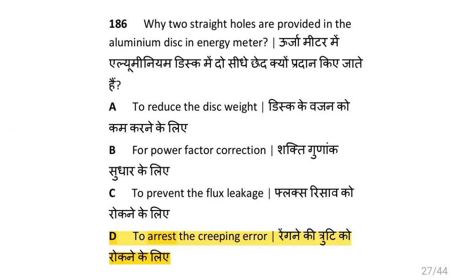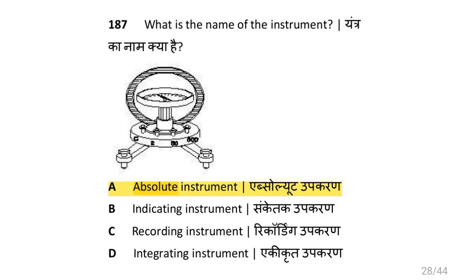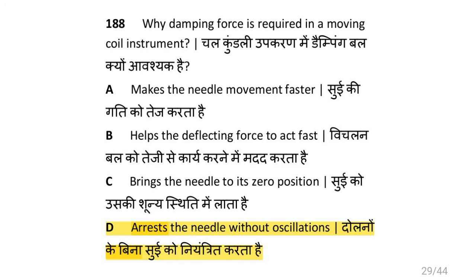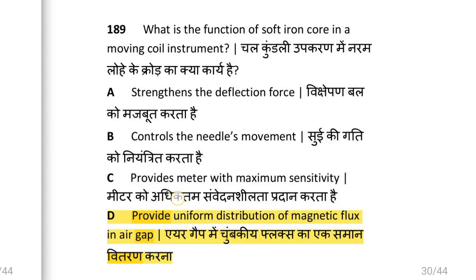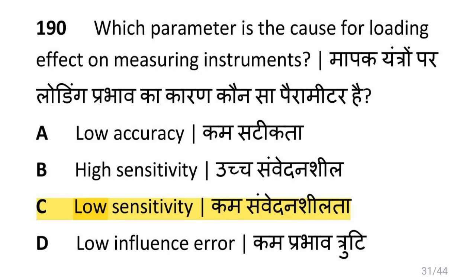Why are two small holes provided in the aluminium disc in an energy meter? To arrest the creeping error. What is the name of the absolute instrument? Tangent galvanometer. Why is damping force required in a moving coil instrument? To arrest the needle without oscillations. What is the function of the soft iron core in a moving coil instrument? That is to provide uniform distribution of magnetic flux in the air gap. Which parameter causes the loading effect on a measuring instrument? Low sensitivity.